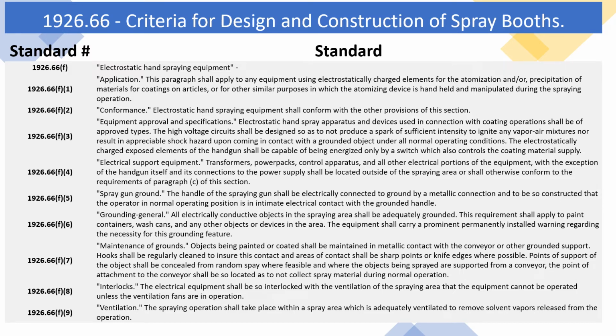1926.66 F3 Equipment approval and specifications. Electrostatic hand spray apparatus and devices used in connection with coating operations shall be of approved types. The high-voltage circuit shall be designed so as to not produce a spark of sufficient intensity to ignite any vapor-air mixtures nor result in appreciable shock hazard upon coming in contact with a grounded object under all normal operating conditions. The electrostatically charged exposed elements of the handgun shall be capable of being energized only by a switch, which also controls the coating material supply.